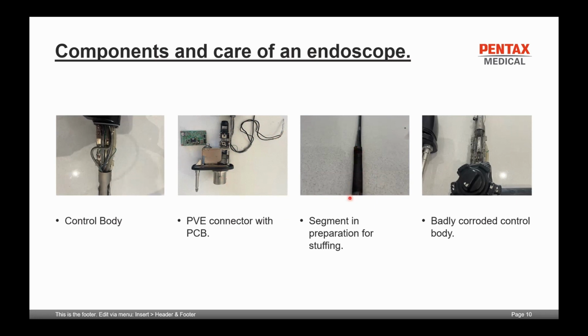This is a segment stay coil assembly that's in preparation of stuffing. So I'm not sure if it's too clear on your side, but as you can see there, all of those wires that are combined there are basically going into your segment stay coil and into your insertion tube. As you can see, it's quite a tight fit, hence the need for molykote powder and graphite powder so that everything can rub smoothly against each other. The last image here, we've got a corroded control body of an endoscope. As you can see, this endoscope has encountered a fluid contamination, and you can see the damage that has occurred from the fluid contamination of the endoscope.